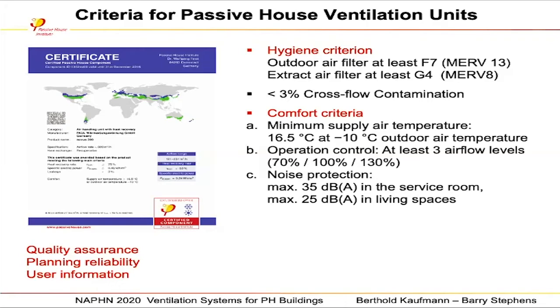Well, the next is you should have your system simple, only about 3 levels of operation, as I mentioned before, 70, 100, and 130. Number C is noise. Please care that the system is not noisy. In living spaces, we ask for 25 decibel A level, and only if it's in a bathroom maybe a little more noisy. Please do it, otherwise people will afterwards maybe complain about too noisy systems.